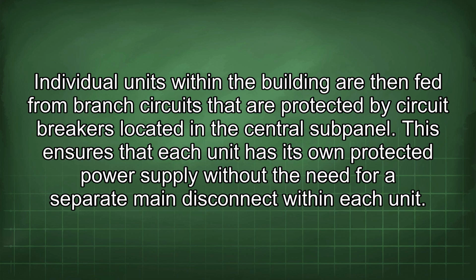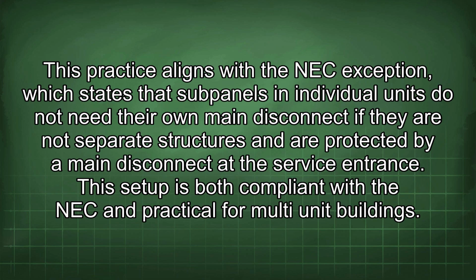This ensures that each unit has its own protected power supply without the need for a separate main disconnect within each unit. This practice aligns with the NEC exception, which states that subpanels in individual units do not need their own main disconnect if they are not separate structures and are protected by a main disconnect at the service entrance. This setup is both compliant with the NEC and practical for multi-unit buildings.